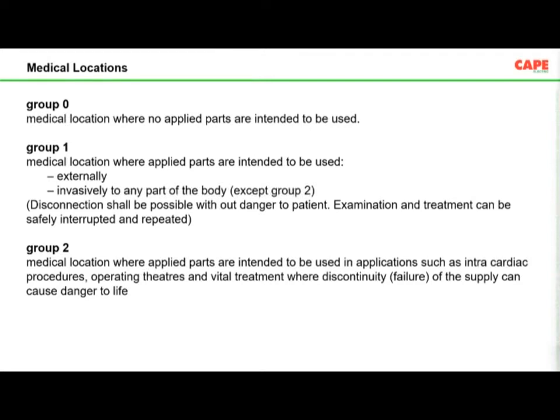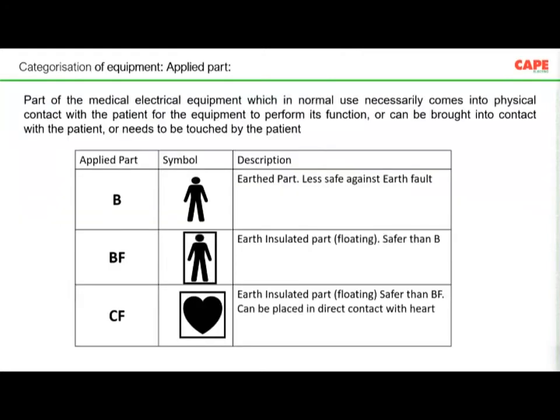So the first point is the medical locations are grouped as per group 0, group 1 and group 2 medical locations in the standard. The next is the applied parts. Applied part means the part of that particular medical equipment which finally is connected to the body of a person. So there are earthed parts, earth insulated parts, and earth insulated parts floating.